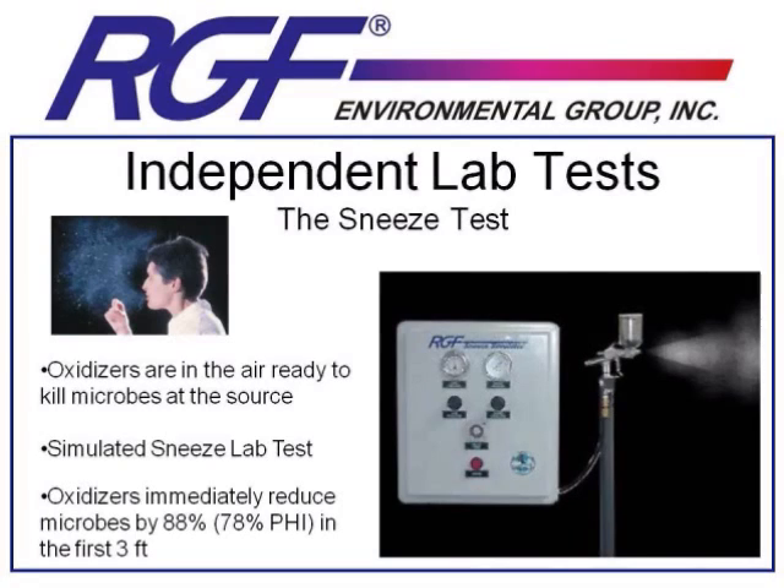Which is exactly what the PHI and REME models are designed to do. We had been doing testing in our own bio chamber with a manual sneeze machine. Sandia Labs asked us to step it up to the next level and build a machine that can exactly simulate a human sneeze — one lung worth of air capacity with one gram of fluid and a known number of microbes. We built our own sneeze machine, pictured here, and had it tested by Sandia Labs and Kansas State University. You would put the sneeze machine in a controlled chamber, fill the air with the same level of oxidizers you would get in a typical residential application, and fire the sneeze machine at a plate three feet away.